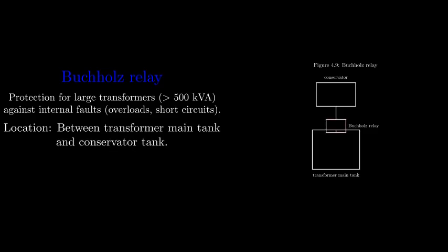This is the Buchholz relay. A Buchholz relay is an oil and gas-activated protection relay, as seen in Figure 4.9. It's used to protect large transformers, typically those bigger than 500 kVA, from internal faults like overloads and short circuits. It's located in the pipe that connects the main transformer tank and the conservator tank. The relay works by detecting gas production, which is a symptom of internal faults. Gas bubbles are produced when the transformer oil overheats.